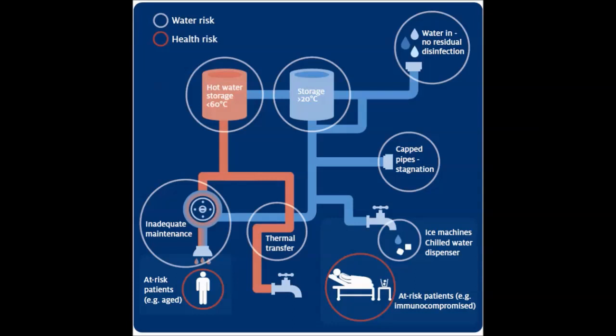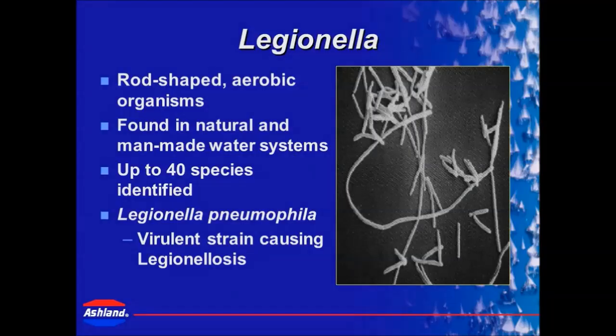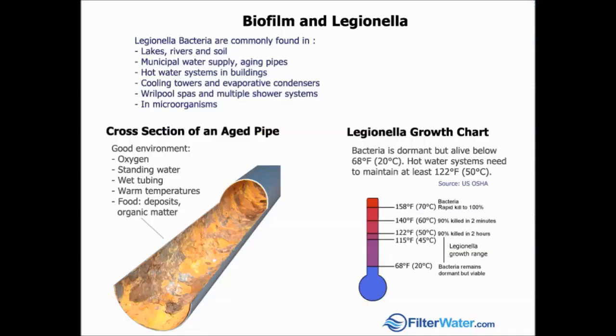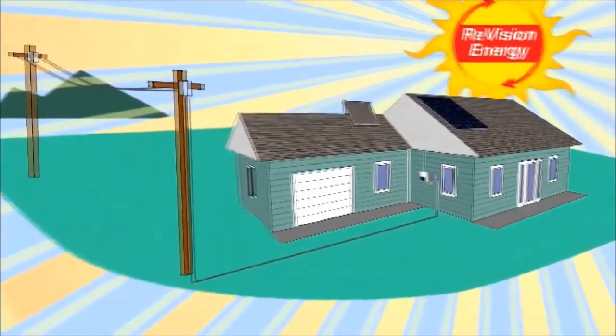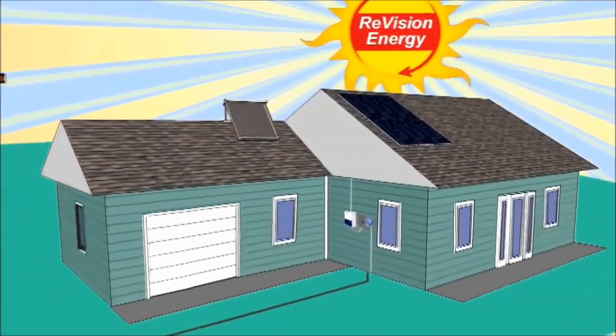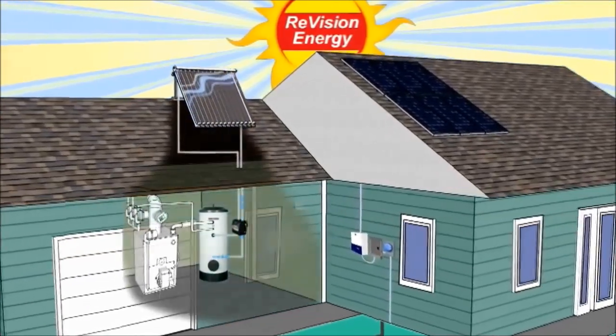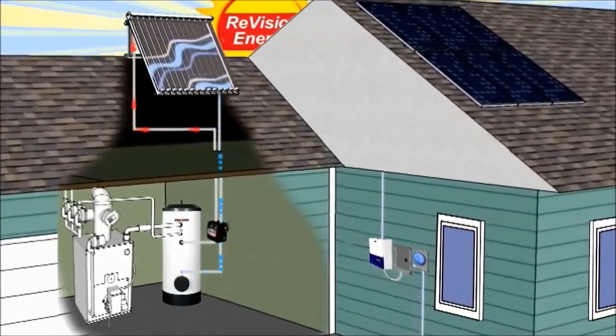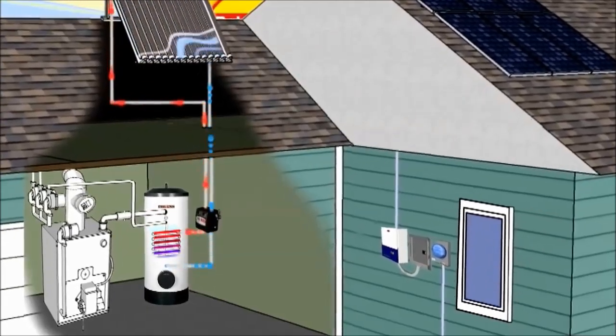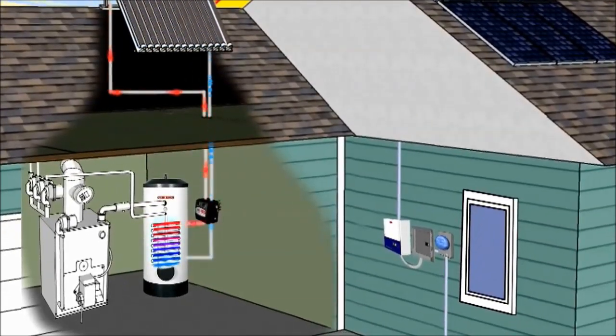A successful water heater will heat and store water at a temperature of 60 degrees Celsius in order to get rid of a certain bacteria called Legionella. This type of bacteria thrives at temperatures between 32 and 35 degrees Celsius, while temperatures over 60 degrees Celsius have a bactericidal effect. Hence, a solar water heater may not be able to heat water to this temperature, especially in winter seasons where hot water is mostly required. This is why a backup electrical heater should be present to cover for the solar heaters in certain situations.